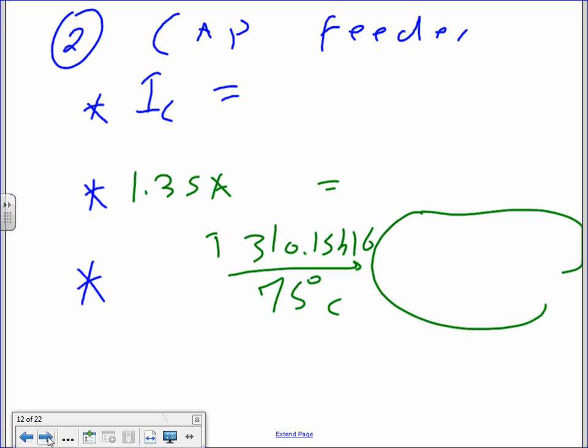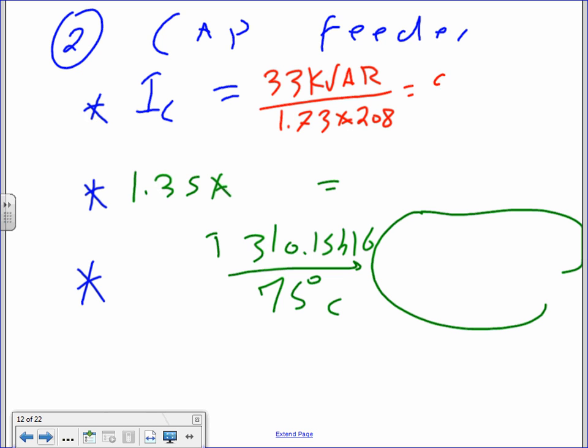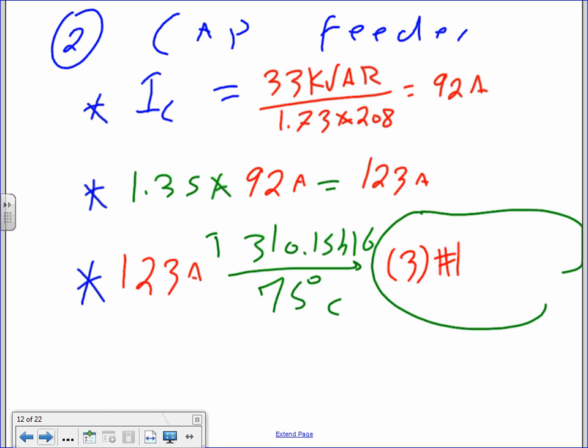All right, so now the rest is history, right? Now you find 33. We're going to repeat ourselves one more time, guys. We take the 33 kvar divided by 1.73 times 208, remember the 208, and you get yourself 92 amps. Multiply the 92 amps by 1.35, that gets you 123 amps. Take the 123 amps to table 310.15(B)(16), 75 degree column, that will get you three conductors, number 1 AWG THHN.